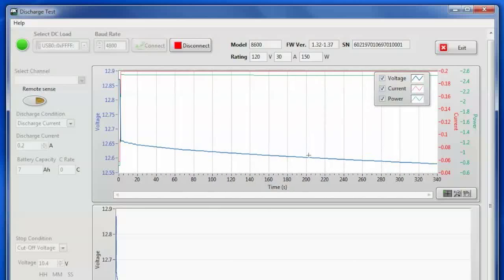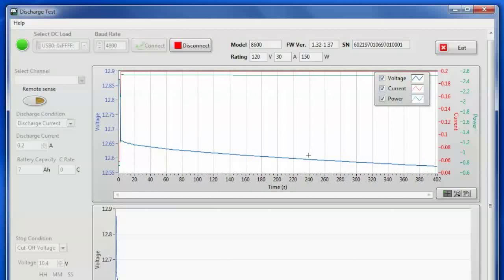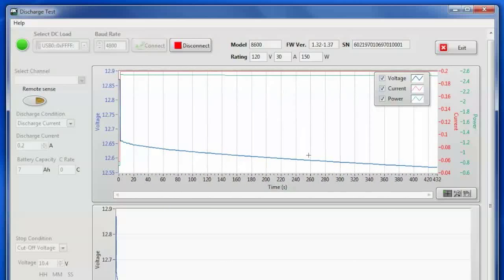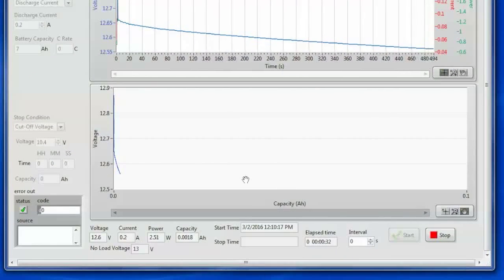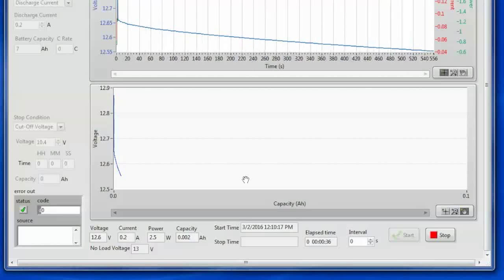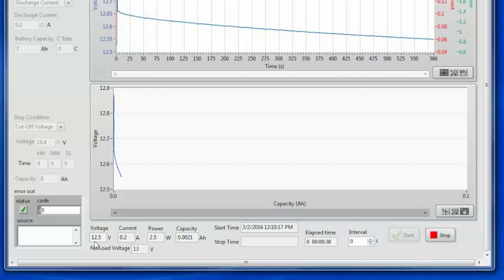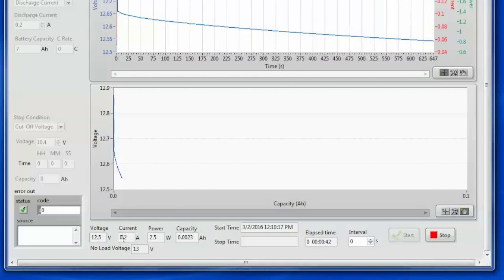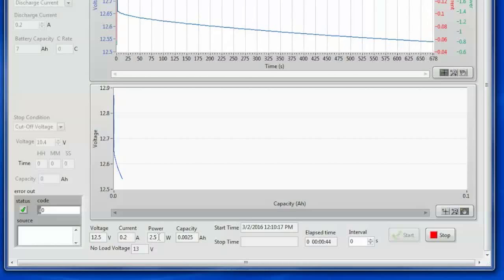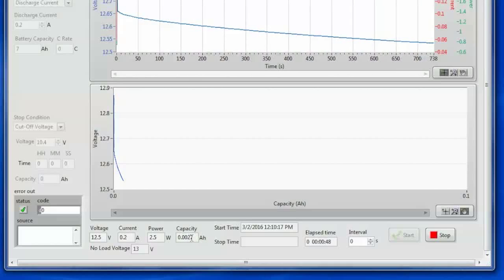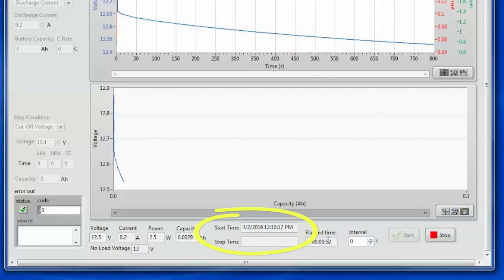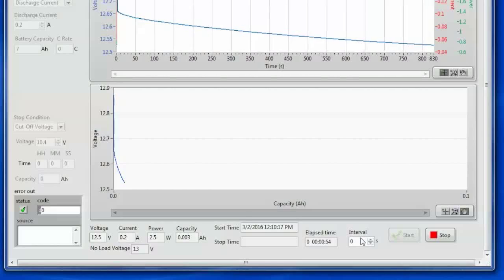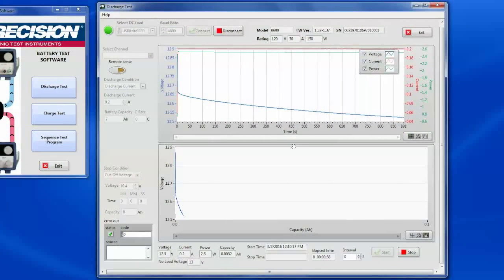At which point the software will automatically stop discharging the battery and will turn off the inputs of the load. Down here on the bottom window you'll see as it discharges over time it'll calculate the amp hour capacity of the battery, which is what I'm trying to figure out right now. The current state of the test is at 12.5 volts, 200 milliamps which is what we've set. And now you can see the power and this amp hour capacity will continue to go up over time. Have the start time, stop time, everything else that will be stamped in the test that we'll be able to retrieve once it's done and it's logged all of the data.